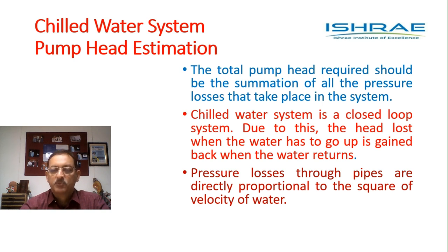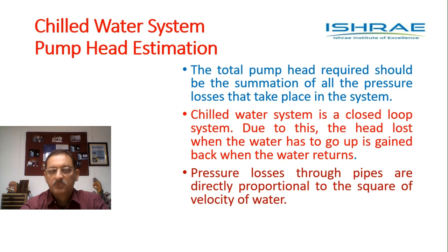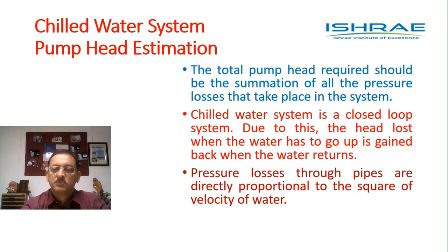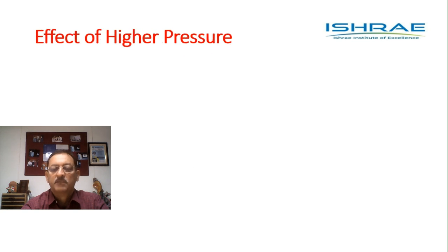This is what we need to remember when sizing the pumps. Pressure losses through pipes are directly proportional to the square of the velocity of water, so the higher the velocity we choose, the more will be the pressure losses. We should choose lower velocities — the maximum velocity as specified in books is three meters per second in pipes, and we should normally remain well within 80 percent of that maximum.